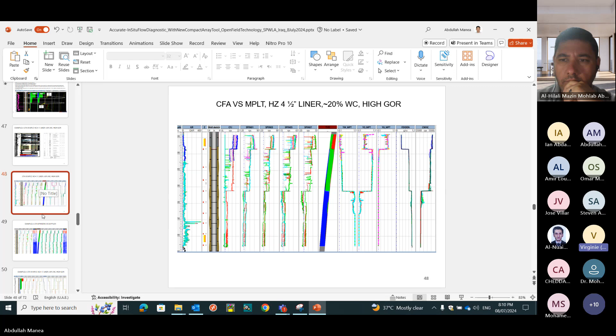Yes, we do, though not always an example we can share openly and on record. For instance, in oil emulsion, that's why we also developed the new capacitance. If we are looking at oil emulsion or high gas rate, we can see that the capacitance tends to perform better for measuring water holdup than the conductivity probes when you have really small water droplets. In terms of hierarchy, it will depend. When you are logging from bottom to top and you see an increase of speed using the spinner, you can see at some point that, for instance, conductivity will stop measuring water holdup. The water holdup will be too small, and then you see the water holdup measurements no longer agreeing.